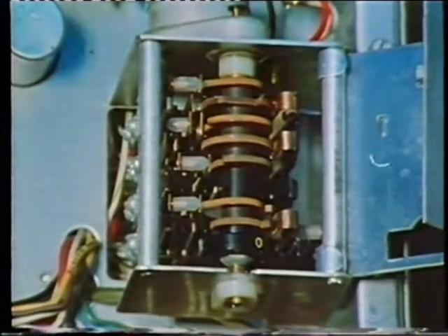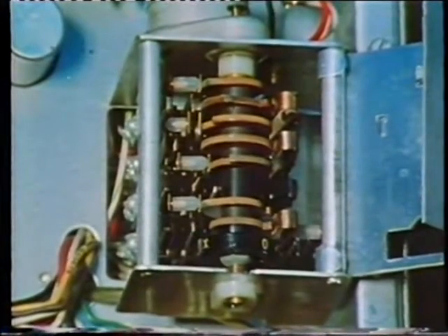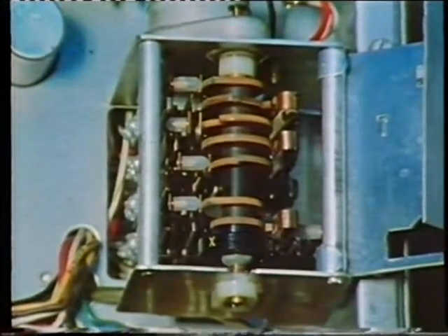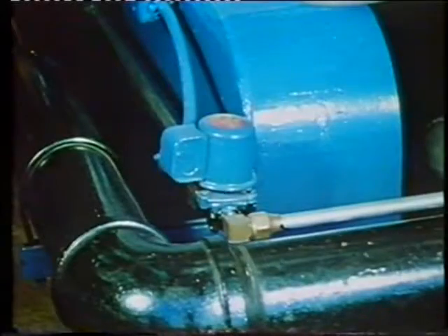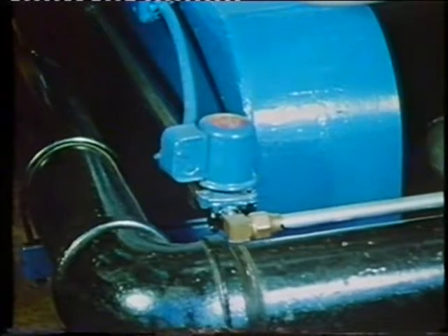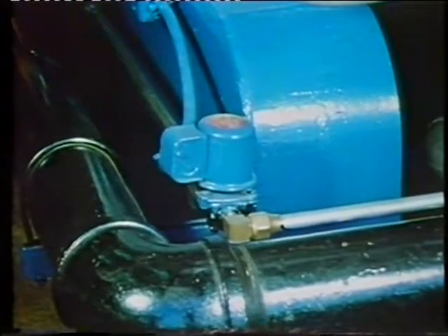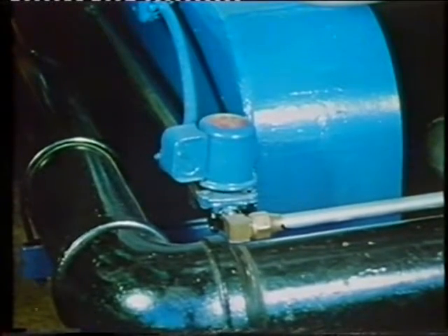Ignition of the fuel oil is accomplished by a gas pilot flame. The gas pilot valve is energized by a signal from the programmer to let gas flow during the ignition period. If the pilot does not ignite when required, the ignition system shuts down. On some boilers, the gas pilot solenoid closes after the main burner flame is established.